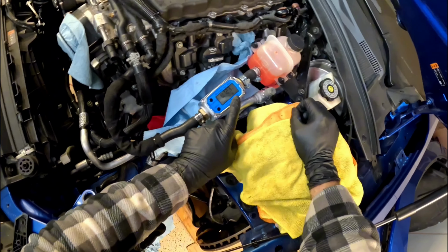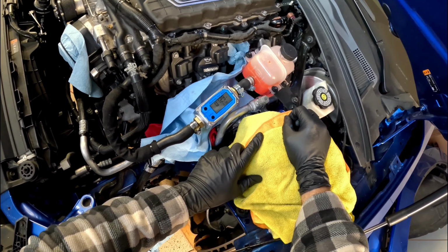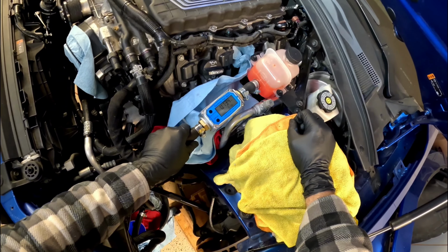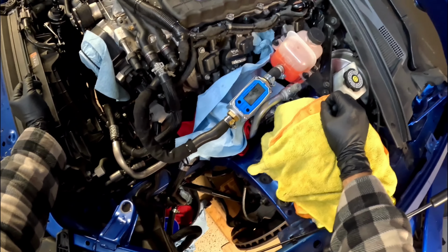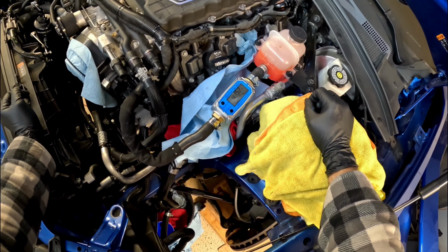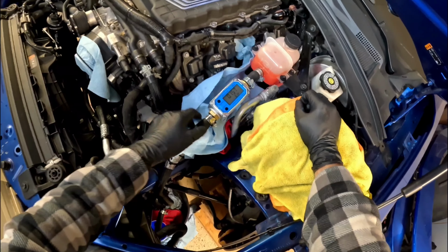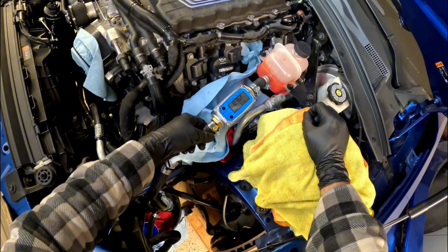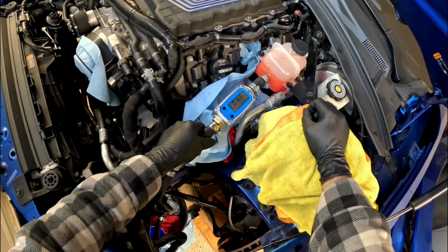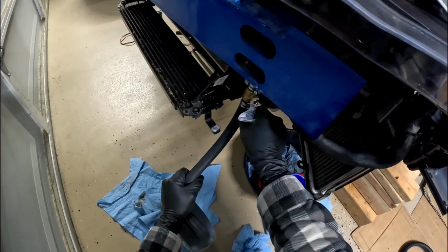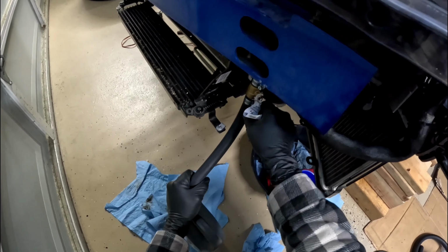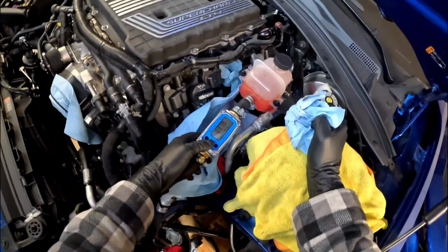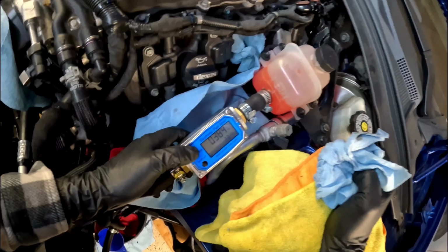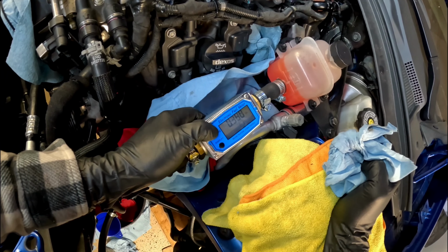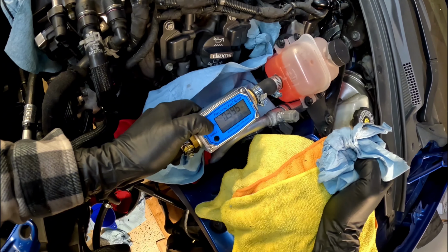So this one only seems to be pumping 0.14, 0.15, 0.14. So that other pump definitely was pushing more fluid, had more flow on it. It's dropped from 0.18 down to 0.14 now. I've now bled off that T to make sure there's no air pocket in there. You can see the flow is just about the same as it was before.